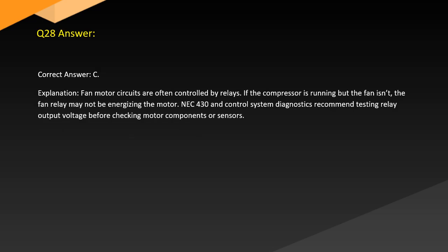Answer. Correct answer C. Explanation. Fan motor circuits are often controlled by relays. If the compressor is running but the fan isn't, the fan relay may not be energizing the motor. NEC 430 and control system diagnostics recommend testing relay output voltage before checking motor components or sensors.